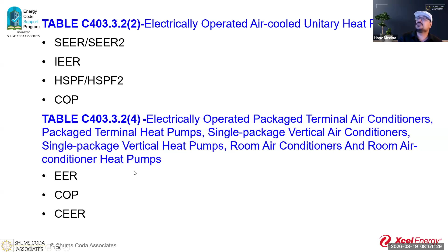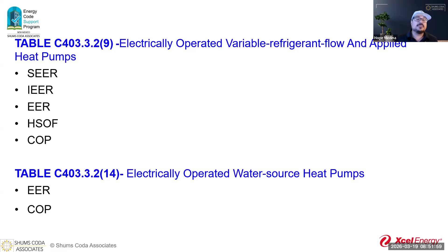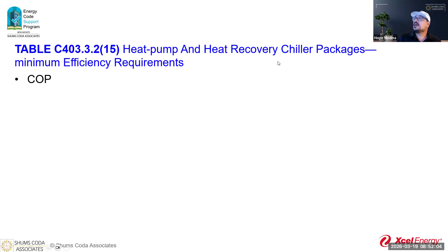Here we have water source heat pumps, with EER and COP. The difference is they're not as affected by seasonal change in their ability to provide cooling, because we're taking advantage of a predictable temperature differential in a ground source heat pump. For heat pump and heat recovery chiller packages, we point to COP.